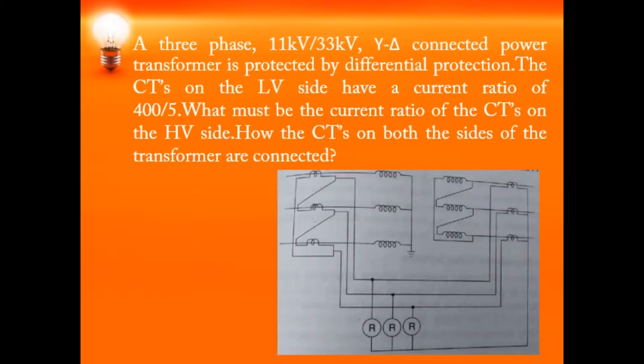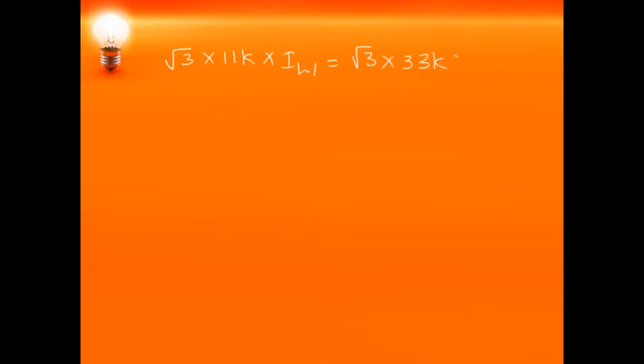Next is a 3-phase 11 kV / 33 kV star-delta connected power transformer protected by a differential protection scheme. The CTs on the LV side have a current ratio of 400/5. We need to find the CT ratio on the HV side and the connection on both sides. Considering primary current as IL1 and secondary as IL2: root 3 × 11 kV × IL1 = root 3 × 33 kV × IL2.